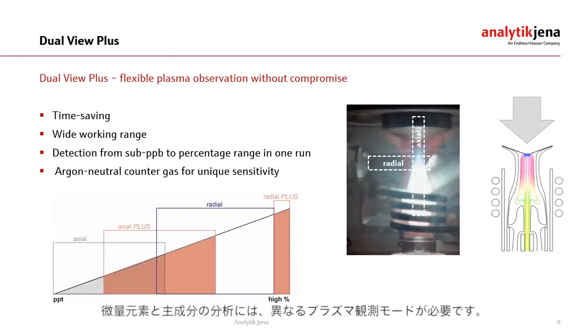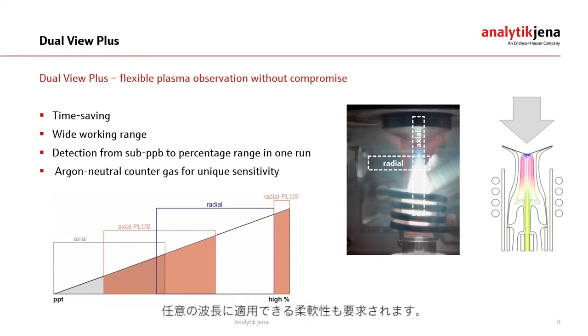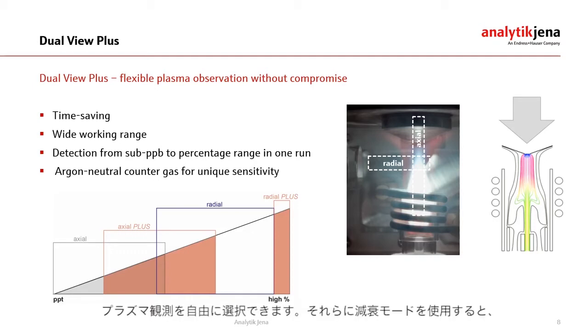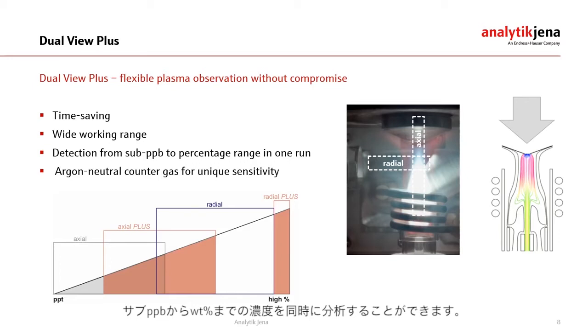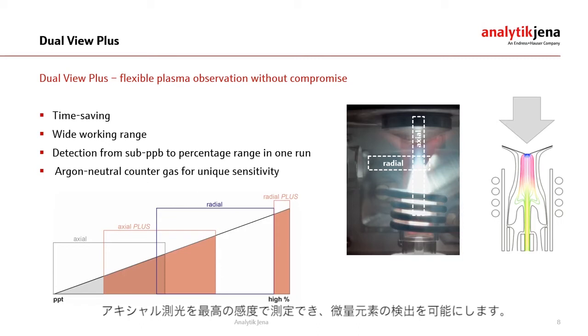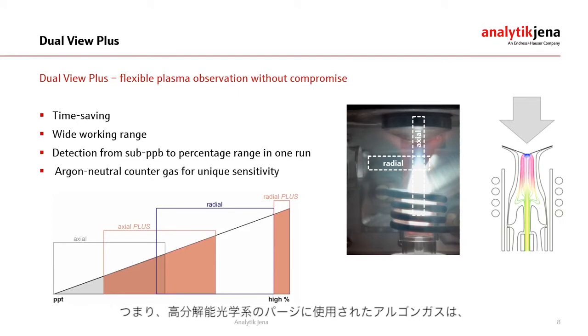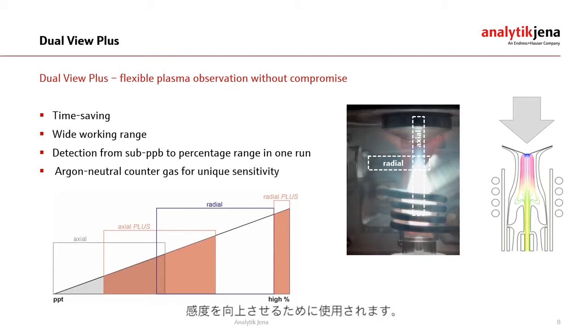The analysis of trace elements and major constituents requires different plasma observation modes and the flexibility to apply any mode to any emission line in a single method. Our dual view plus option enables free selection of the radial and axial plasma view and additionally allows use in an attenuated mode. With this concept it is possible to perform synchronous analysis of contents ranging from the sub-ppb to the high weight percent. The intelligent argon neutral counter gas technology provides highest sensitivity in axial observation, using the argon that purges the high resolution optics to remove the plasma tail, which is known to cause spectral interferences and reduce overall sensitivity.